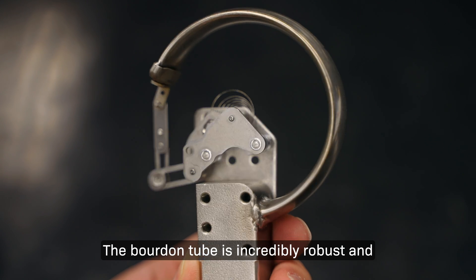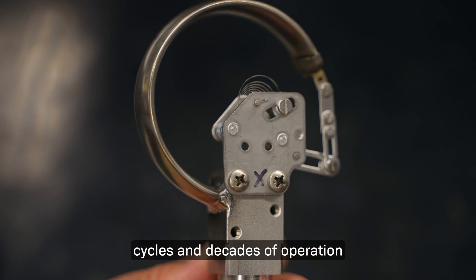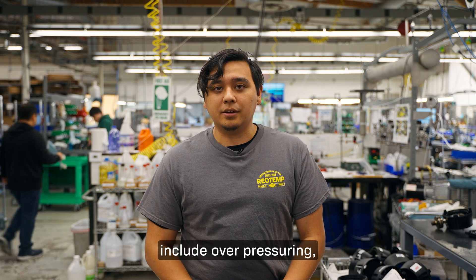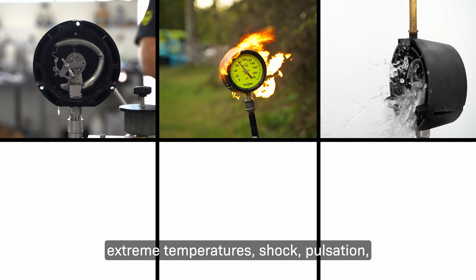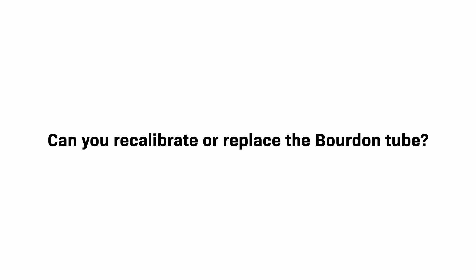How long do Bourdon tube pressure gauges last? The Bourdon tube is incredibly robust and can last millions of cycles and decades of operation under normal conditions. Conditions that lead to a shorter lifespan include overpressuring, extreme temperatures, shock, pulsation, vibration, corrosion, and clogging.